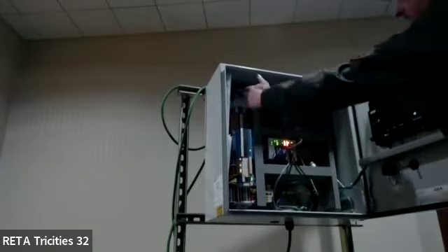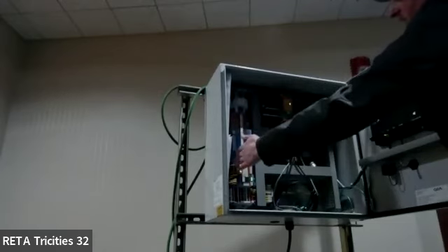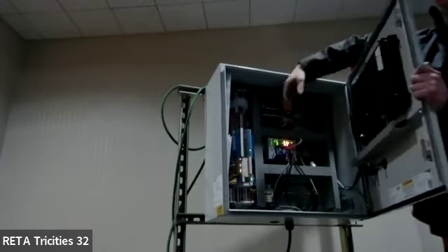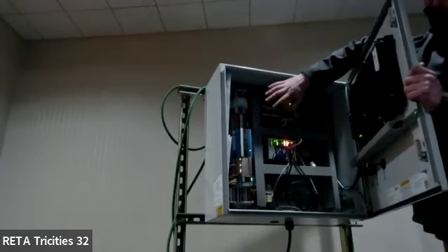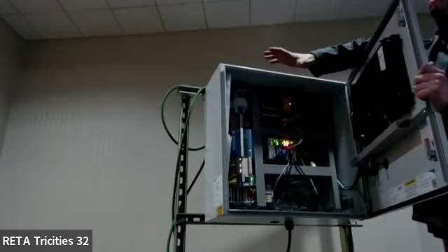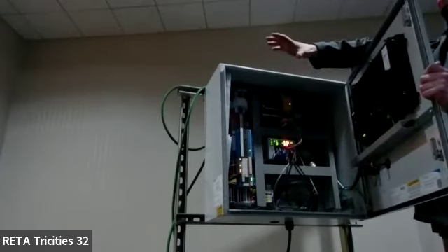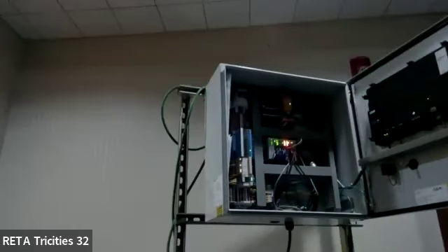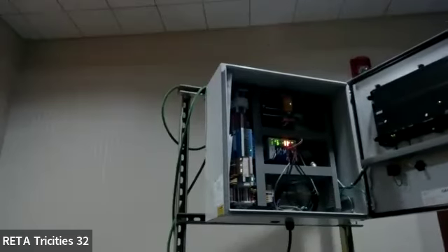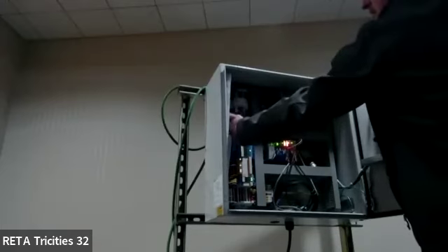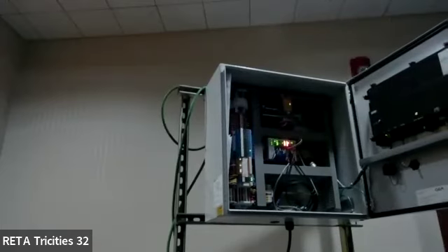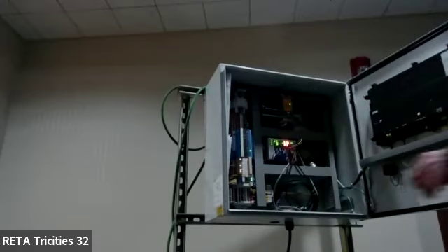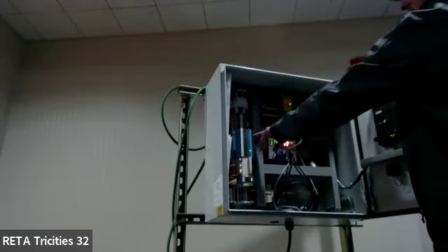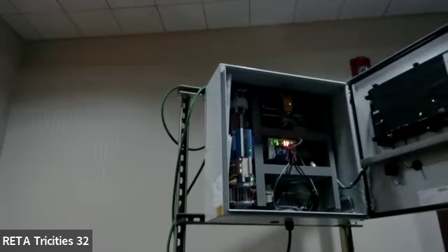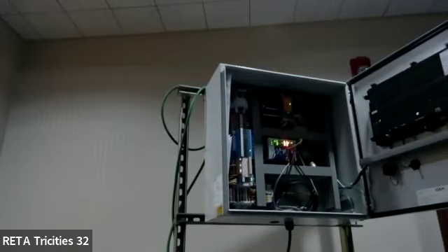This is where all the digital is right here. A mistake I've seen a lot of people make is when they're trying to add, like, what's this say, an economizer solenoid. And it's a 120 volt solenoid. This side, these relays, the coils and the relays are 24 volt. So if you were to wire that solenoid onto this side, you're going to short it.